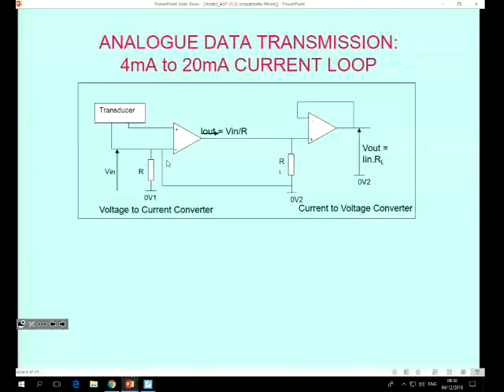rather than 0 to 5 volts or 0 to 15 volts? It's easier to tell a fault, really - yeah, that's the main reason. If you get a 0 in a 4 to 20 milliamp loop, you know that that's a fault. If you get a 0 in a 0 to 5 volt circuit, it could be a true measurement, or it could just be that there's no measurement there. So 4 to 20 milliamps is really good, because if the wire's broken at all, you're going to get nothing, and you'll know straight away it's broken.